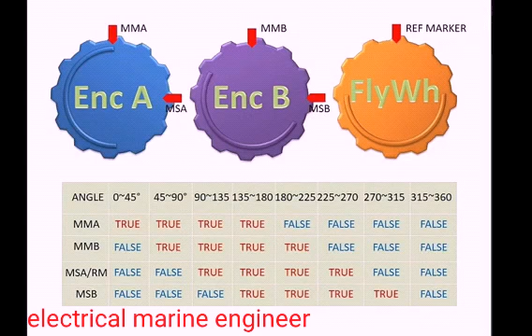In this system, instead of sensor MSA in encoder A, the flywheel sensor is used as a reference sensor. The reason is that there is a chance of error in the encoder A and encoder B sensors getting slipped from the shaft. But the flywheel sensor is a fixed one and will not get error at any time. So we are using this sensor as a reference sensor to calibrate the other sensors. This is the reason the flywheel sensor is given. I hope you understand all the features of this encoder, how it is working, and how useful it is for finding the exact position.